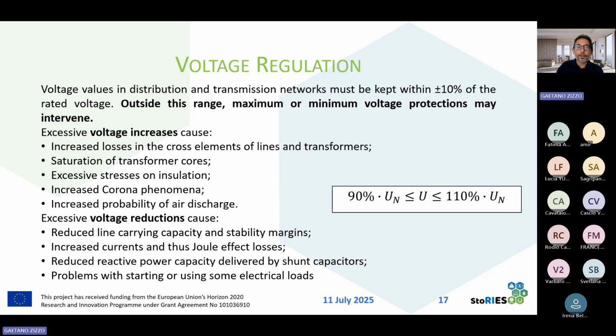An excessive voltage increase can cause increased losses in the cross elements of lines and transformers, can cause saturation of transformer cores, excessive stress of insulation of cables, for example, increased corona phenomena with increased losses, and increase the probability of air discharge, in particular for over the lines. While an excessive voltage reduction can cause reduced line carrying capacity and stability margins.